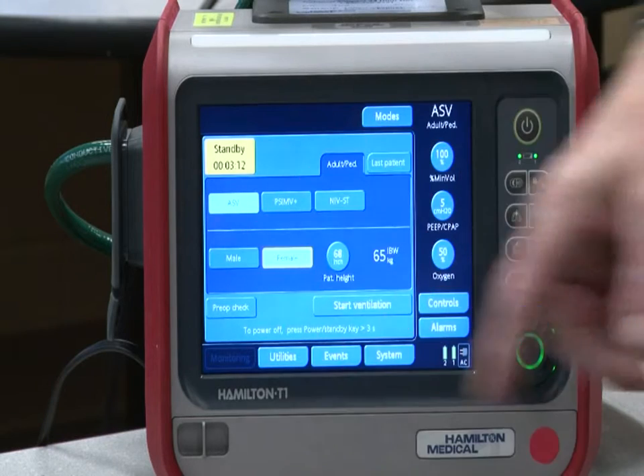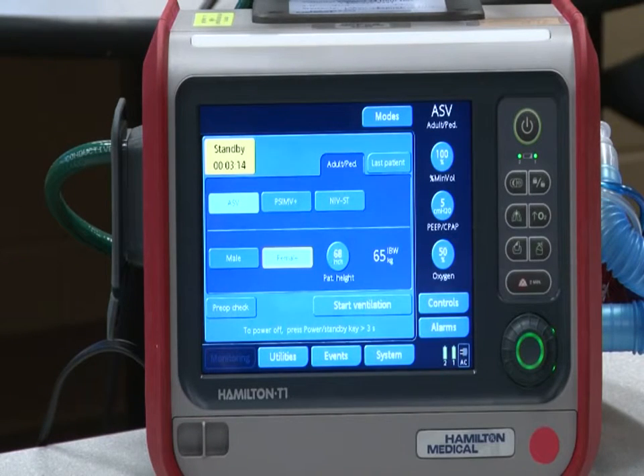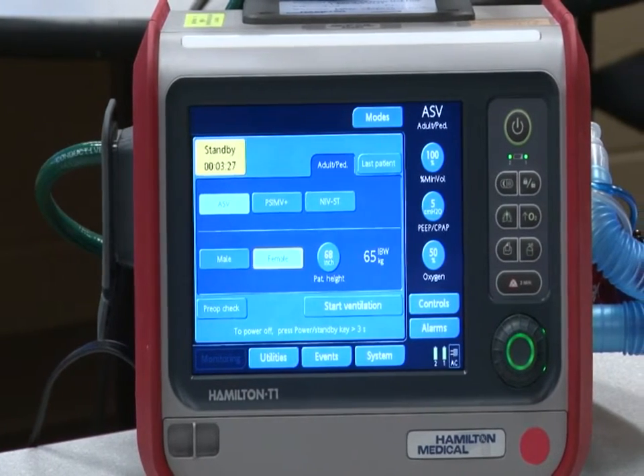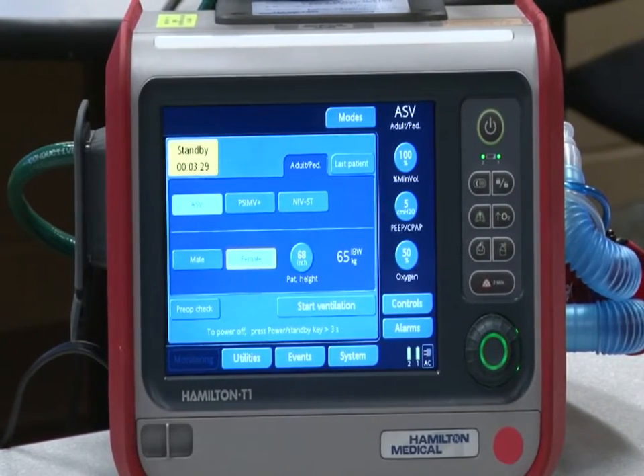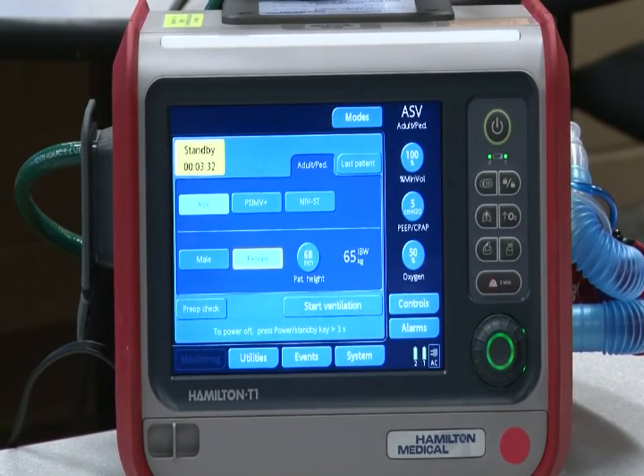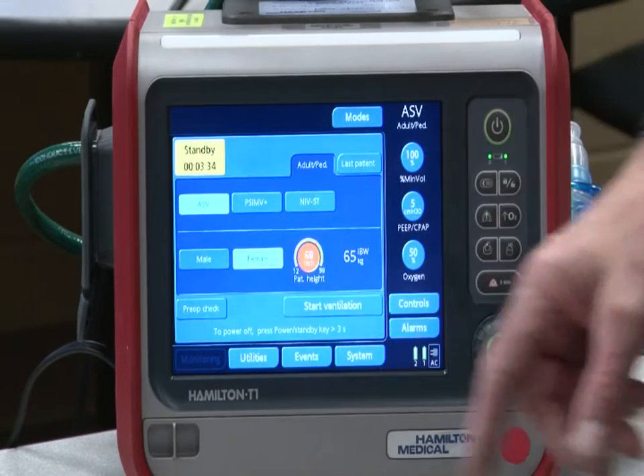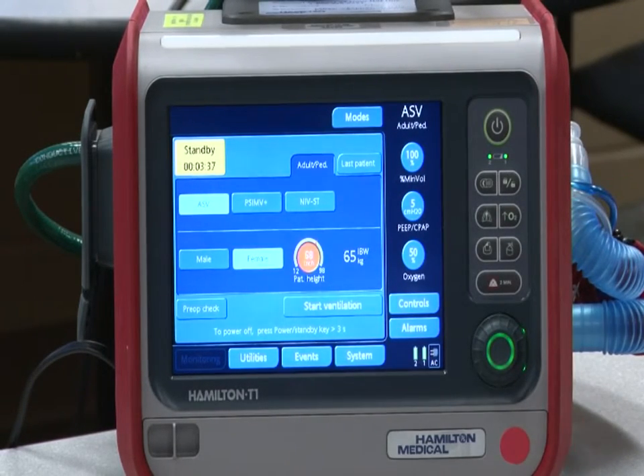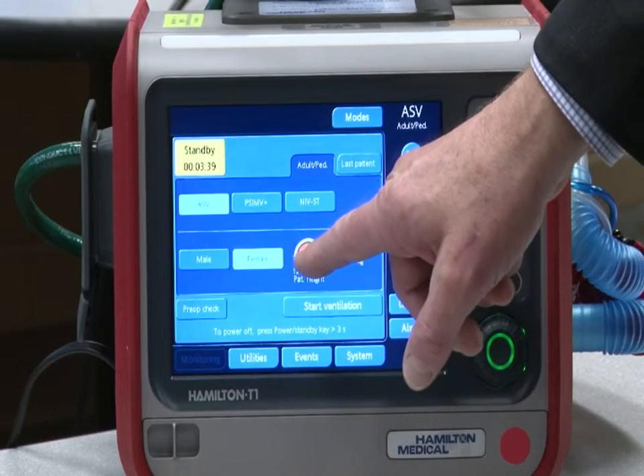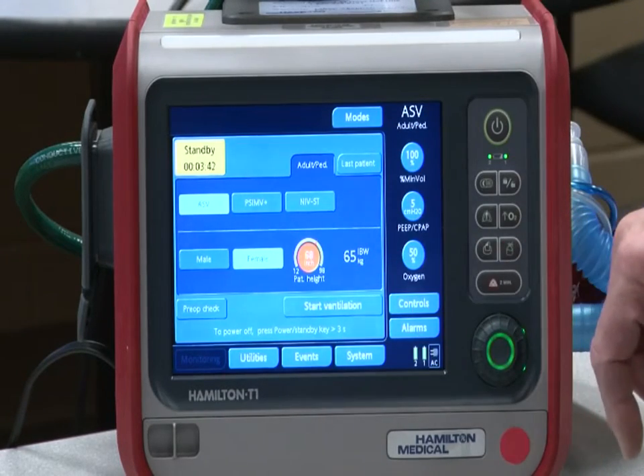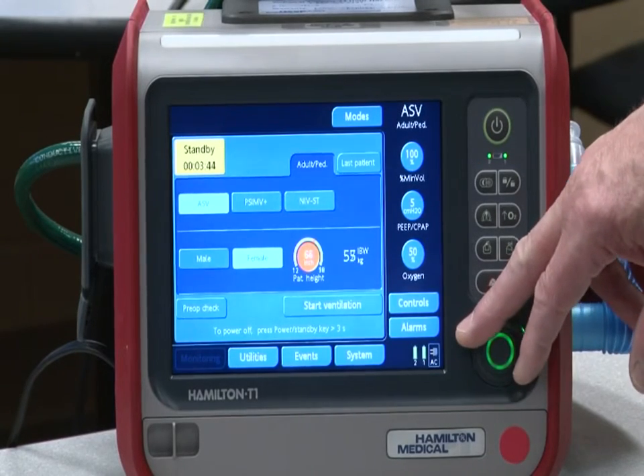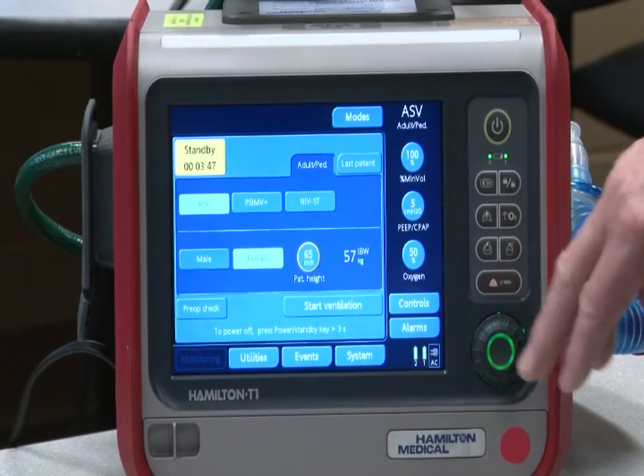But if we select, let's pick a female patient. So the short form instruction for using the ventilator is touch what you want to change. Okay, so that's the second takeaway. When in doubt, touch something, and if it's something that's going to be fairly significant, you're going to have to touch it twice to confirm that that's what I want to do, or it's going to turn orange. Okay, so let's put in a female patient that's 5'5". So if I selected female, and now by touching the height, which should be in inches, because we've configured it that way for you, let's turn that down until we get a patient that's 5'5", which would be 65 inches.